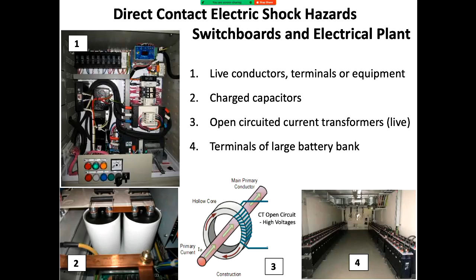Now, something you've probably not seen before is current transformers. Have you done anything on current transformers at all? A current transformer is basically a bus bar going through, which is like one turn, and then you've got multiple turns. If this is 100 amps and you've got 100 turns there, then you'll get 1 amp coming out there. The only issue, of course, is that that's in the amperage. But if those are open circuited, you've got 1 to 100, so this can become a very high voltage. You might think you're on the secondary side, in a cabinet, not high voltage stuff, but you can create high voltages with CTs, and that's why they always get shorted when you have to maintain them.